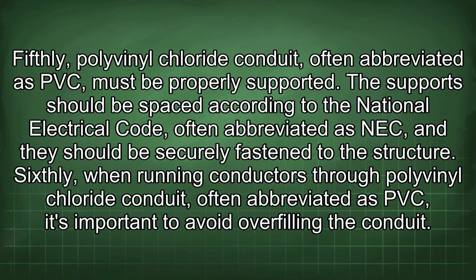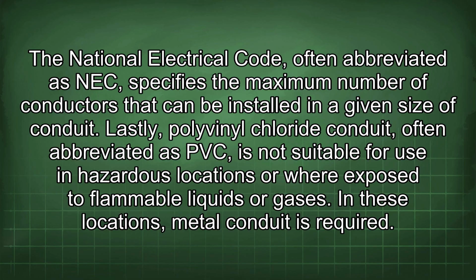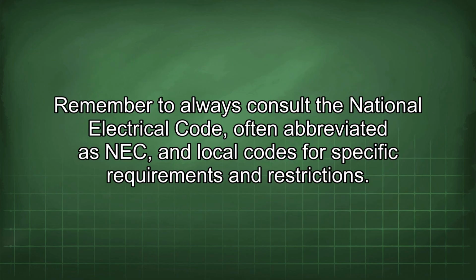Sixthly, when running conductors through PVC, it's important to avoid overfilling the conduit. The NEC specifies the maximum number of conductors that can be installed in a given size of conduit. Lastly, PVC is not suitable for use in hazardous locations or where exposed to flammable liquids or gases. In these locations, metal conduit is required. Remember to always consult the NEC and local codes for specific requirements and restrictions.